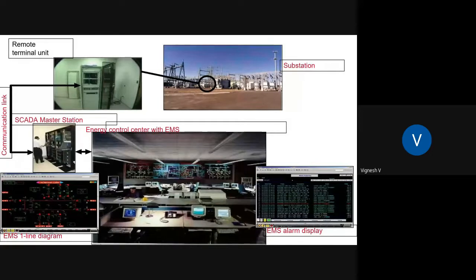For example, if you have to open a breaker, it issues a command, and that command is communicated back to the substation. So this is a kind of closed loop operation. We sense, we run some algorithms, and we issue a control command back, and then we see the effect. It's completely a closed loop system, even now with SCADA.